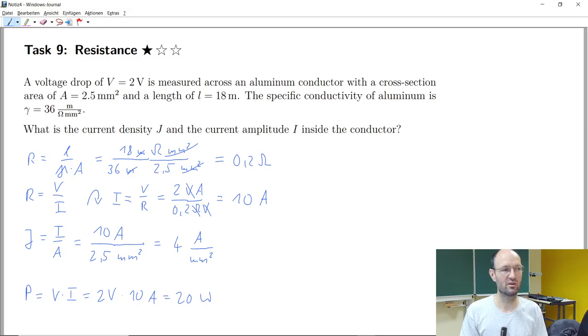And so now you can imagine, okay, 20 watts is not too much, but it is something. And it depends on what is the surrounding of the cable. Is the surrounding able to dissipate this heat and spread it into the environment. And if you have the 18 meter cable also wound onto a reel, and if it's isolated somewhere, and if you for a longer time, let's say 24 seven heated up with 20 watts, then it will also get hot over time and it might destroy the cable.